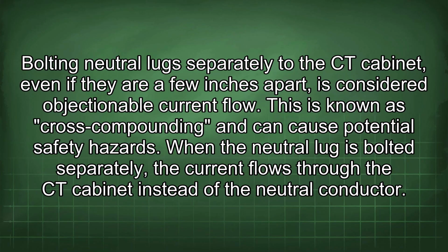Bolting neutral lugs separately to the CT cabinet, even if they are a few inches apart, is considered objectionable current flow. This is known as cross-compounding and can cause potential safety hazards. When the neutral lug is bolted separately, the current flows through the CT cabinet instead of the neutral conductor.